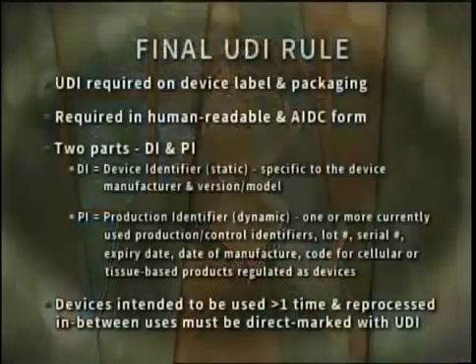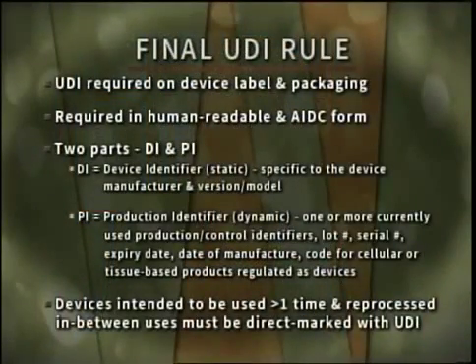But as Dennis mentioned, the long-awaited rule came out September 24th of this year. UDI will be required on the device label and packaging, of course, barring exception, which I'll get into in a moment. The UDI is required in a human-readable form and then an AIDC, or automatic ID and data capture, form.